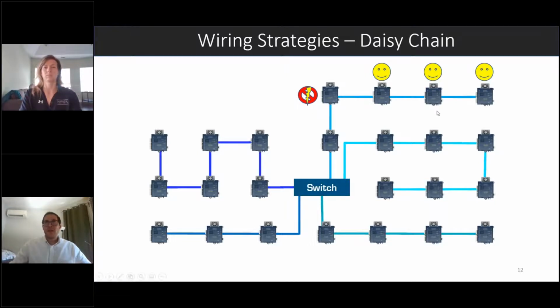And also, the rule of 50 comes into play in that usually you don't want to have more than 50 controllers. That's probably a pretty consistent hard cutoff with a lot of manufacturers: 50 controllers on a daisy chain IP link. So the shorter you keep these little daisy chain links, that is usually the preferred strategy. You're not going to be concerned about the amount of data throughput along that entire communication chain.